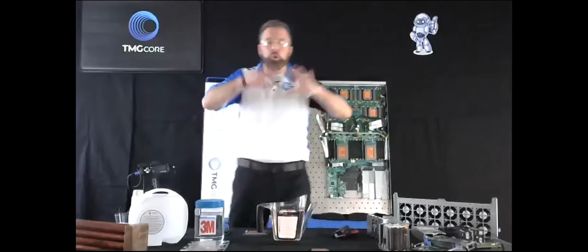So two-phase liquid immersion cooling at a high level needs the infrastructure of the tank units themselves — electrical, mechanical, security, control software, interface, so you can control it remotely or locally through the HMI. You need the fluids, these great fluids from companies like 3M and Solvay, and you also need the hardware. We've developed the hardware — we don't develop the fluids, we have great companies who do that, and we help develop this stuff too. So the auto-ready servers come from companies like Intel, Dell, and Supermicro and others, and we also develop the cooling, the plates and things like that as part of the hardware, and the tank units themselves. We focus on the hardware and the tank units, working with material suppliers and manufacturers like Jabil and Vertiv, great companies manufacturing these things for us. There's the actual tank units themselves, making sure they're QA'd, QC'd, reliable, manufactured properly, and release tested.